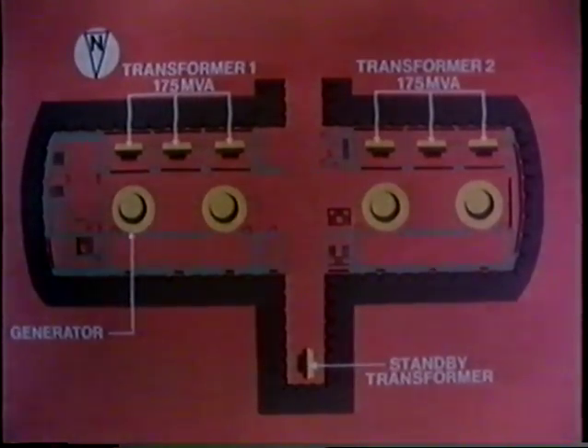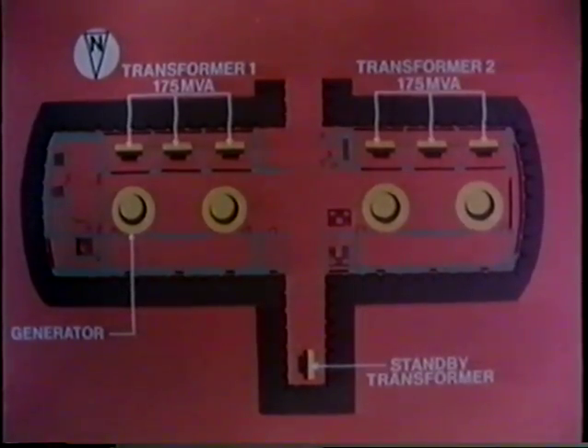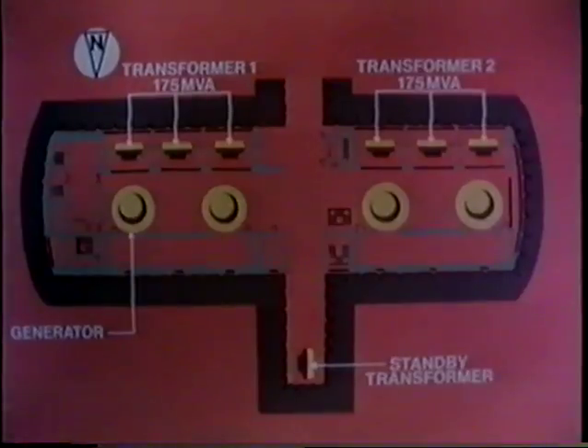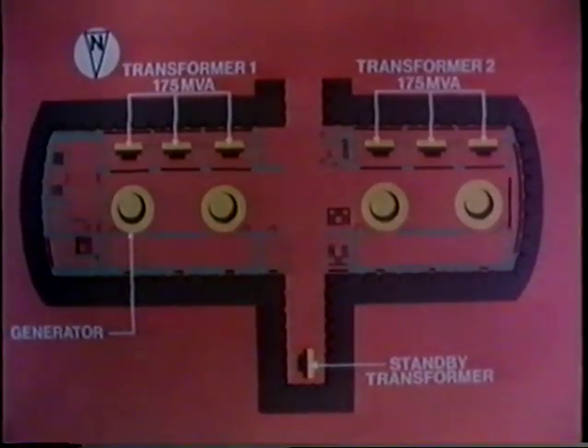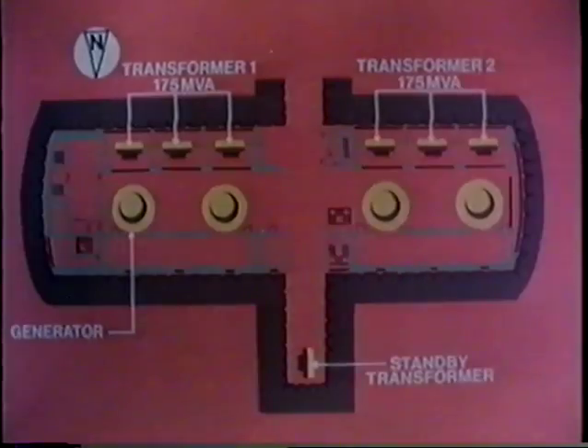Two large three-phase units would have required greater cavern width and a larger access tunnel, so in this case, the multiple units are the more economic. Another advantage is that one extra single-phase unit can be conveniently stored in the cavern, readily available as a replacement for any of the other six. Each single-phase unit is housed in a separate cubicle at main floor level.